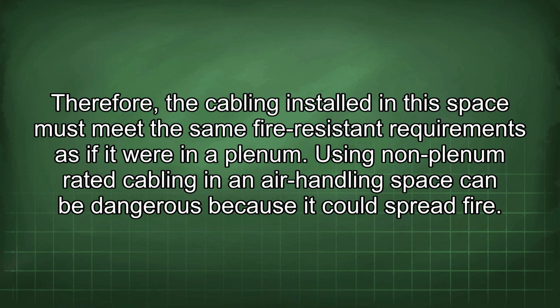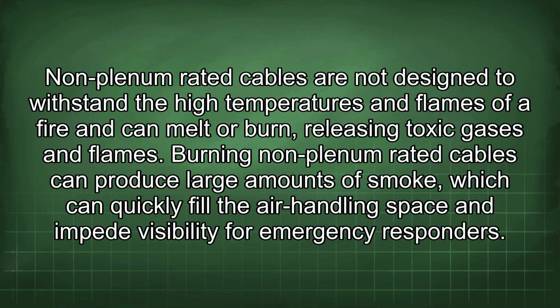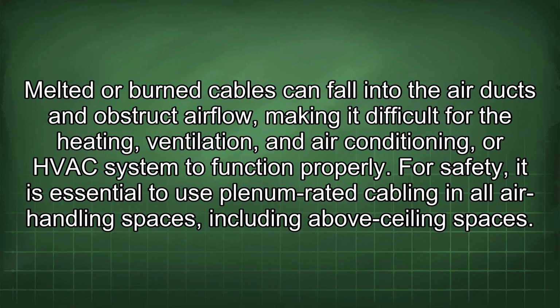Using non-plenum rated cabling in an air handling space can be dangerous because it could spread fire. Non-plenum rated cables are not designed to withstand the high temperatures and flames of a fire and can melt or burn, releasing toxic gases and flames. Burning non-plenum rated cables can produce large amounts of smoke, which can quickly fill the air handling space and impede visibility for emergency responders. Melted or burned cables can fall into the air ducts and obstruct airflow, making it difficult for the heating, ventilation, and air conditioning, or HVAC, system to function properly. For safety, it is essential to use plenum-rated cabling in all air handling spaces, including above ceiling spaces.